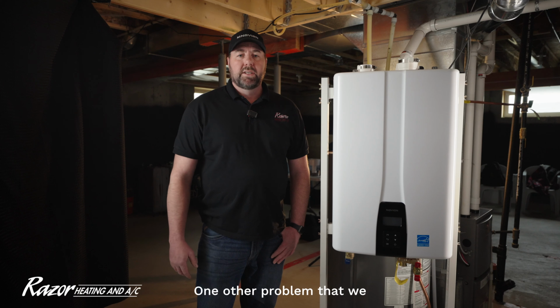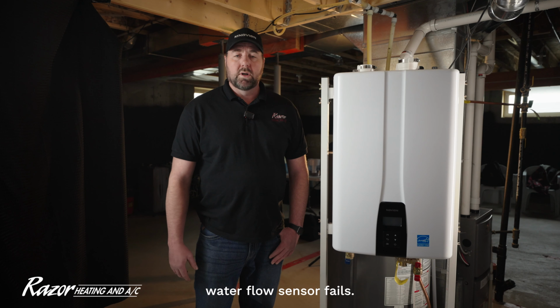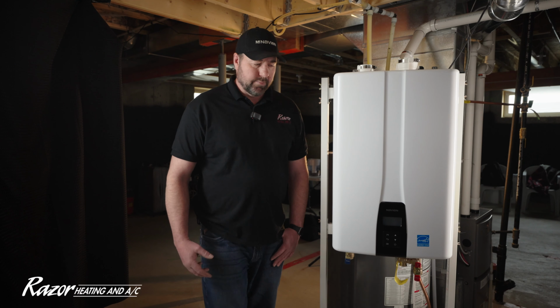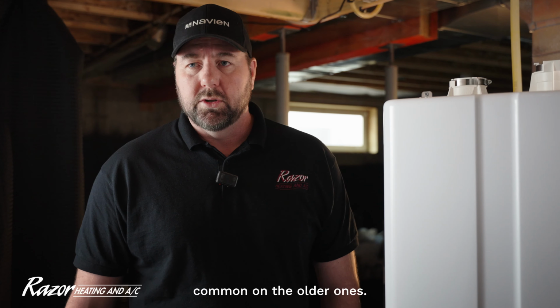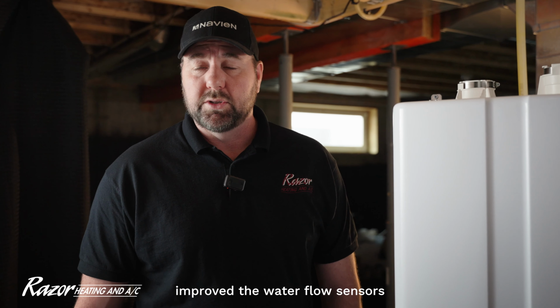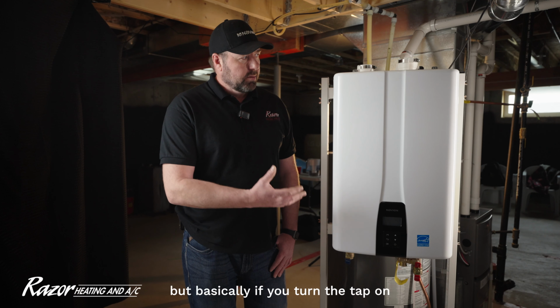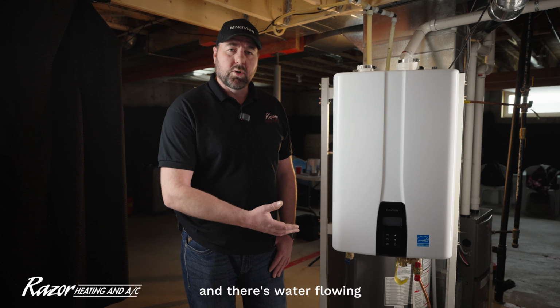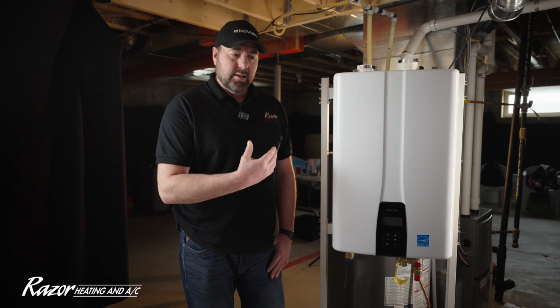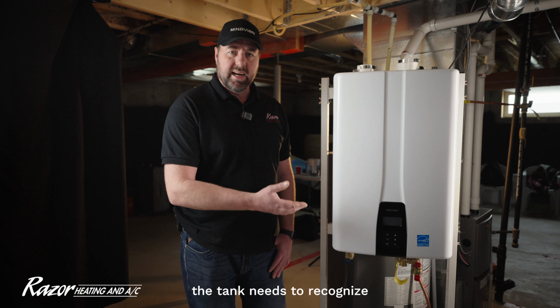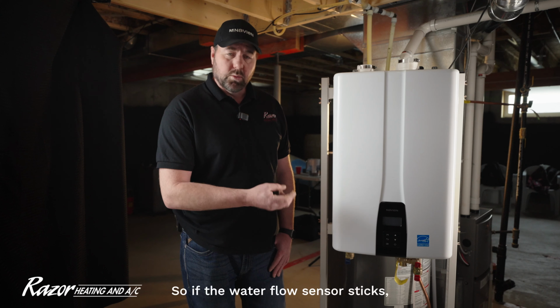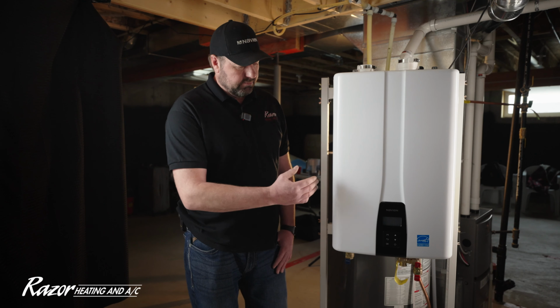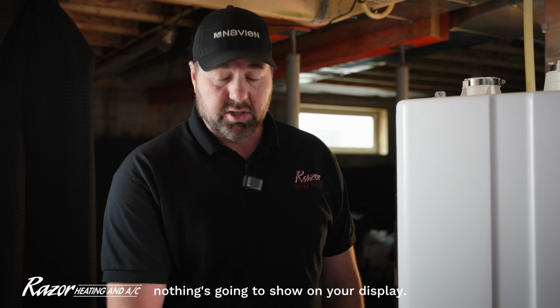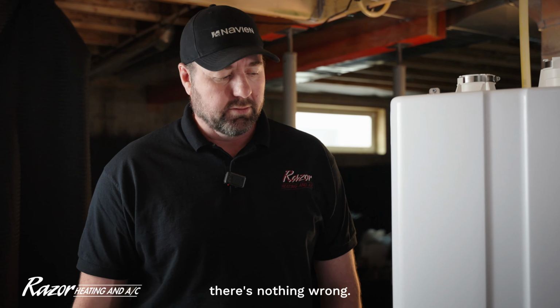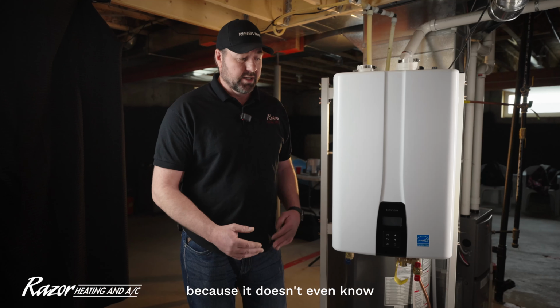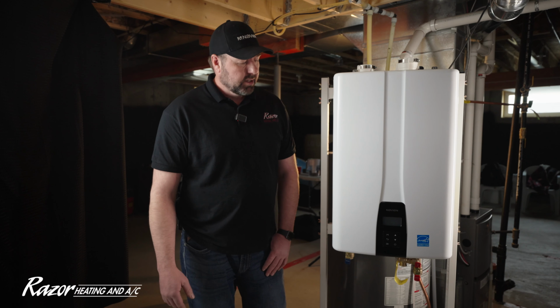One other problem that we see on tankless water heaters a lot of times is the water flow sensor fails. It's definitely more common on the older ones. They seem to have improved the water flow sensors on the new ones, but basically if you turn the tap on and there's water flowing through the water heater, the unit needs to recognize that there's water flowing. So if the water flow sensor sticks, nothing's going to show on your display. It's going to look like there's nothing wrong. There's not going to be an error code or anything because it doesn't even know there's water going through it.